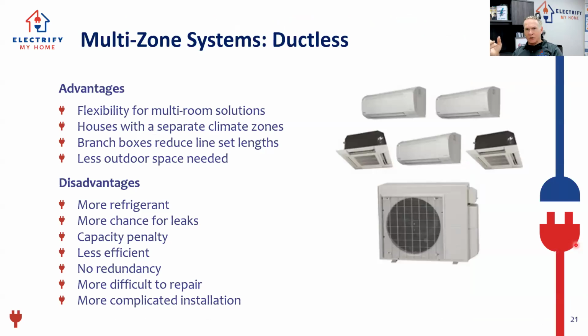So the advantages of multi-zone, they are flexible for multi-room solutions, but think of them this way. If you've got a house that has 3 bedrooms and it has two needed in a living space, let's put a ducted unit in for the 3 bedrooms, control those all off one unit, and then by the way, I can get a duct into the bathrooms that way, so we can handle that. So I got one little ducted system back there. Probably do it with a 9 or a 12,000 BTU at the most. And then I do a 3 zone with 2 heads, and I got that ducted unit. That's a way better solution than putting 5 of these on here. I've now just eliminated what, 8 refrigerant connections and a whole bunch of refrigerant.